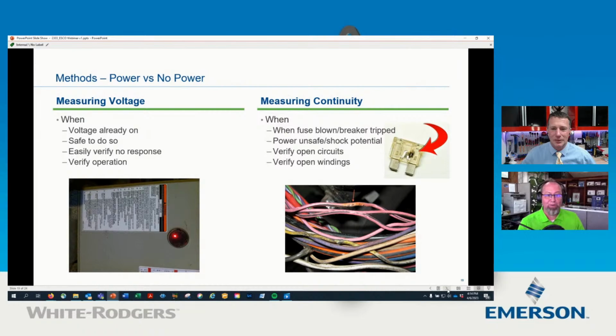If you're not getting 24 volts, it's back somewhere else. If you are getting the 24 volts, hey, the gas valve's getting a signal, it's not opening. And at that point, you've got to have a gas valve issue. Your final verification, the only other thing you can really do on a gas valve, is to put a manometer on the outlet side and see if, when 24 volts is applied, any gas is coming out.